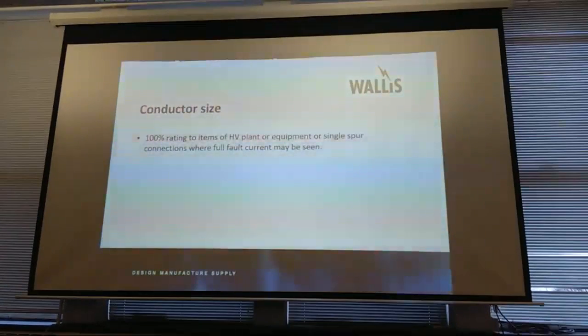Again, the different standards give you different guidance. There's not a great deal mentioned in 50522 about how to connect equipment up, whereas TS 41-24 actually gives you a little bit more guidance. It's a little bit more practical. It gives you a bit more help, and that does say, along with Western Power specs as well, you should have 2 fully rated connections from the earth system to your HV plant.